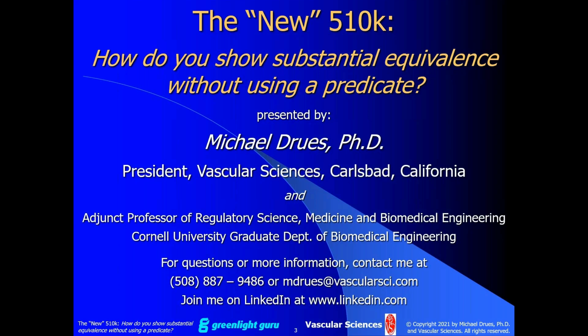But Courtney, coming back to your original question, in a general sense, there could be some exceptions. And if you are thinking of an exception, feel free to contact me. I'm happy to talk to you about it in more detail. But I don't usually see the intended user, whether it's an individual person or a doctor, or the intended use environment, whether it's a home or a hospital, as part of the substantial equivalence argument most of the time. But of course, there are exceptions to every rule.